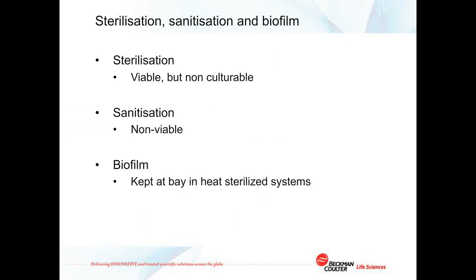Heat sterilization of water systems tends to control the proliferation of biofilm and microbial contamination. Microbes living in a heat sanitized water system are generally unable to replicate to form a colony, and hence the term commonly heard these days: viable but non-culturable. Ozone sanitization, however, actively oxidizes the organic material in the water, including the microbes themselves, and removes life and its source of nourishment from the water system if used correctly, leading to true sanitization of the water system. Biofilm can build in heat sterilized systems, and though it's kept under control by frequent heat sterilization, its presence can form a challenge when switching from an established heat sterilized system over to ambient water manufacturing using reverse osmosis.